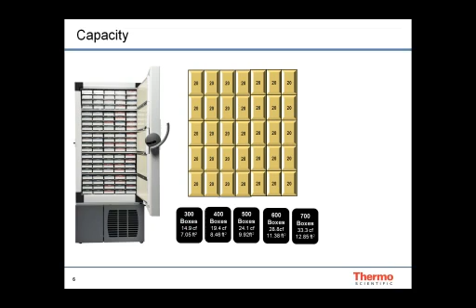So in this case, what you're looking at is the unit design. Every unit has the same height and the same depth. The only thing we change is width, and that's based on the rack design itself. So we have a model 300 that holds 300 boxes, 400 that holds 400 boxes, 500, 600, and then the largest capacity unit in the marketplace holds 700 boxes, 70,000 2-milliliter vials, or 119,300 1-milliliter dense storage vials. So again, great capacity in a much smaller footprint. All of our units will go through a standard 36-inch doorway. So no modifications are needed to get any of these units in.